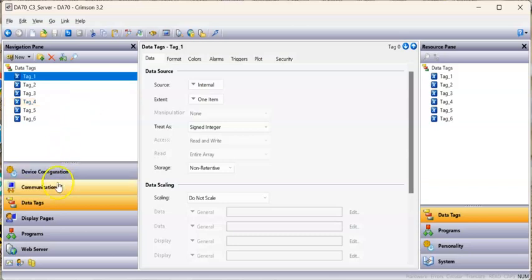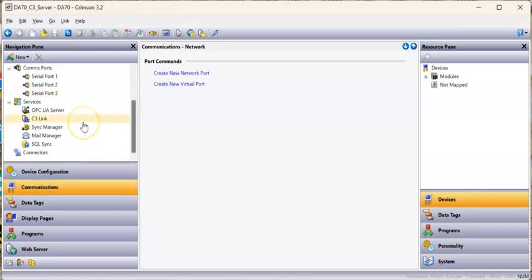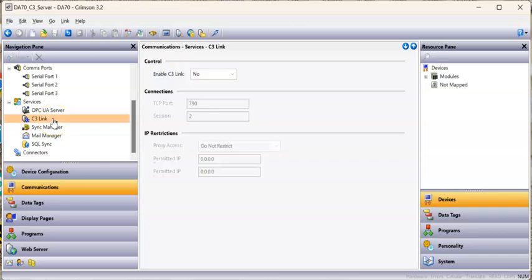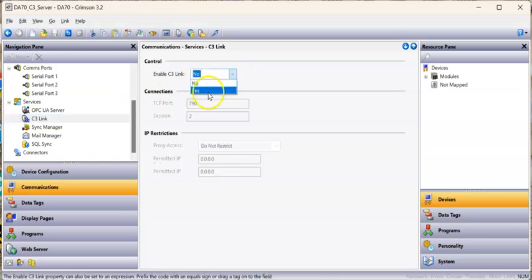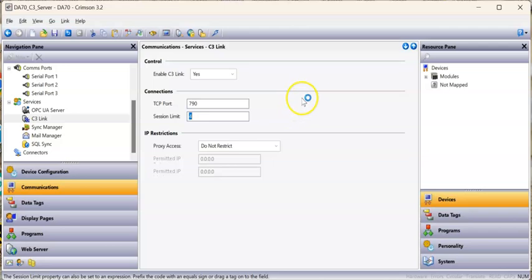If I go over here to communications on the left and slide all the way down into the service section, there's a thing called the C3 Link. I'm going to enable the C3 Link here. I'll leave the port number 790. I might change the session limit to 4, default is 2. And that's it.